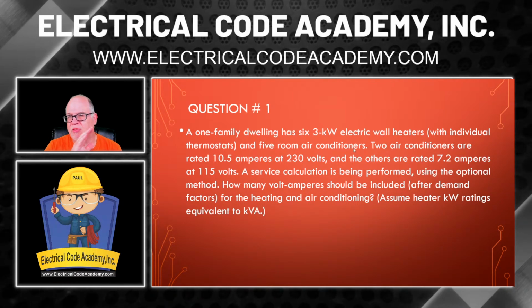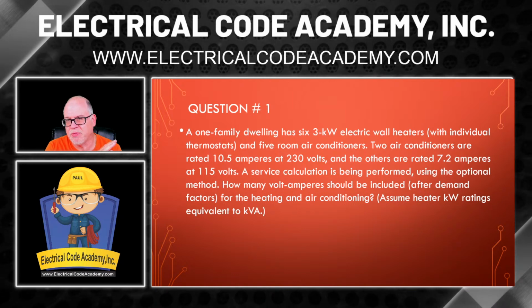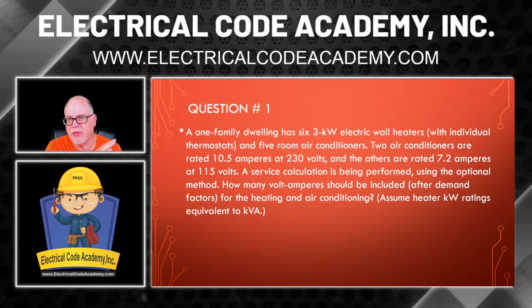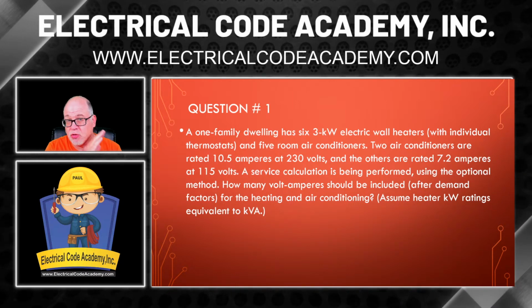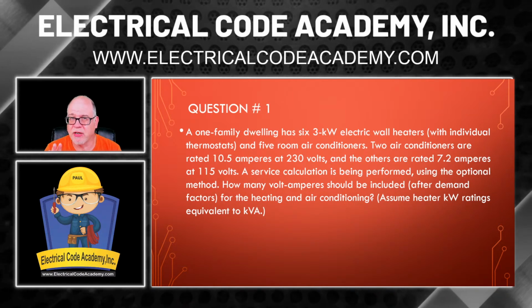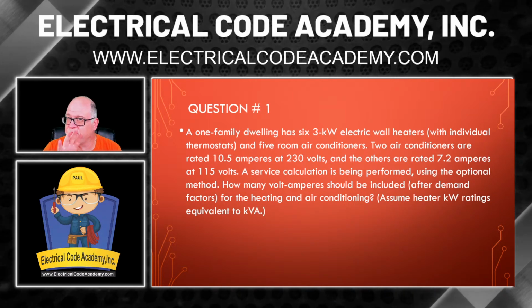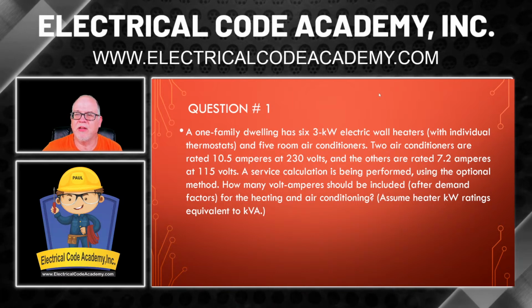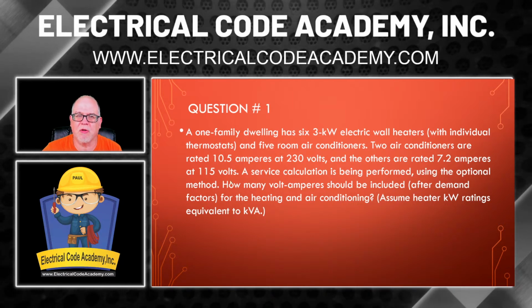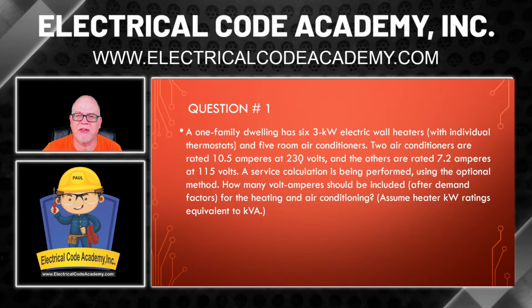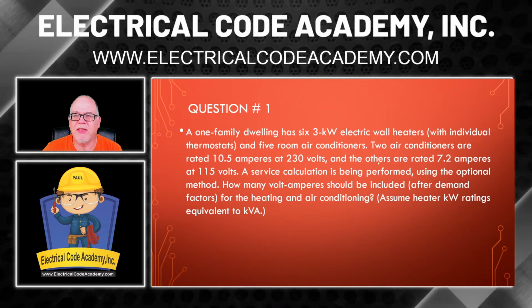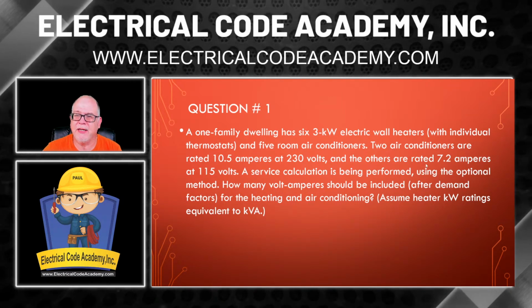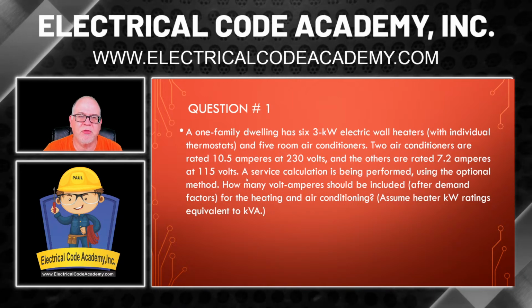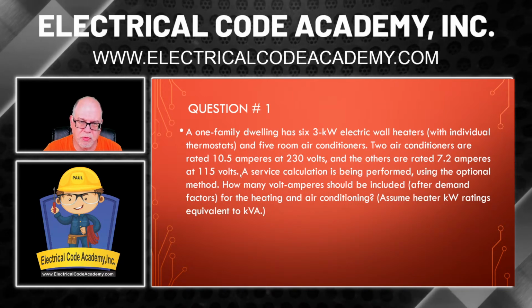So we have 6 3 kW heat strips, each individually thermostatically controlled, and we have 5 air conditioners. Of these 5 air conditioners, 2 are rated 10.5 amperes at 230 volts. And the others, the other 3, are rated at 7.2 amperes at 115 volts.